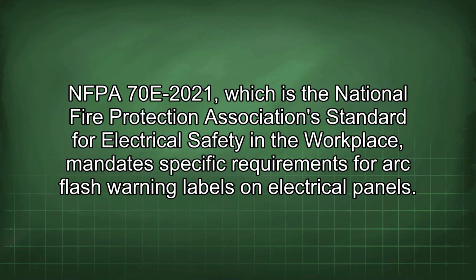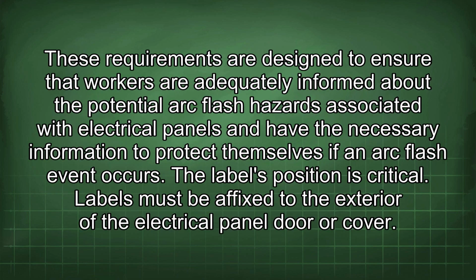NFPA 70E-2021, which is the National Fire Protection Association's standard for electrical safety in the workplace, mandates specific requirements for arc flash warning labels on electrical panels. These requirements are designed to ensure that workers are adequately informed about the potential arc flash hazards associated with electrical panels and have the necessary information to protect themselves if an arc flash event occurs.